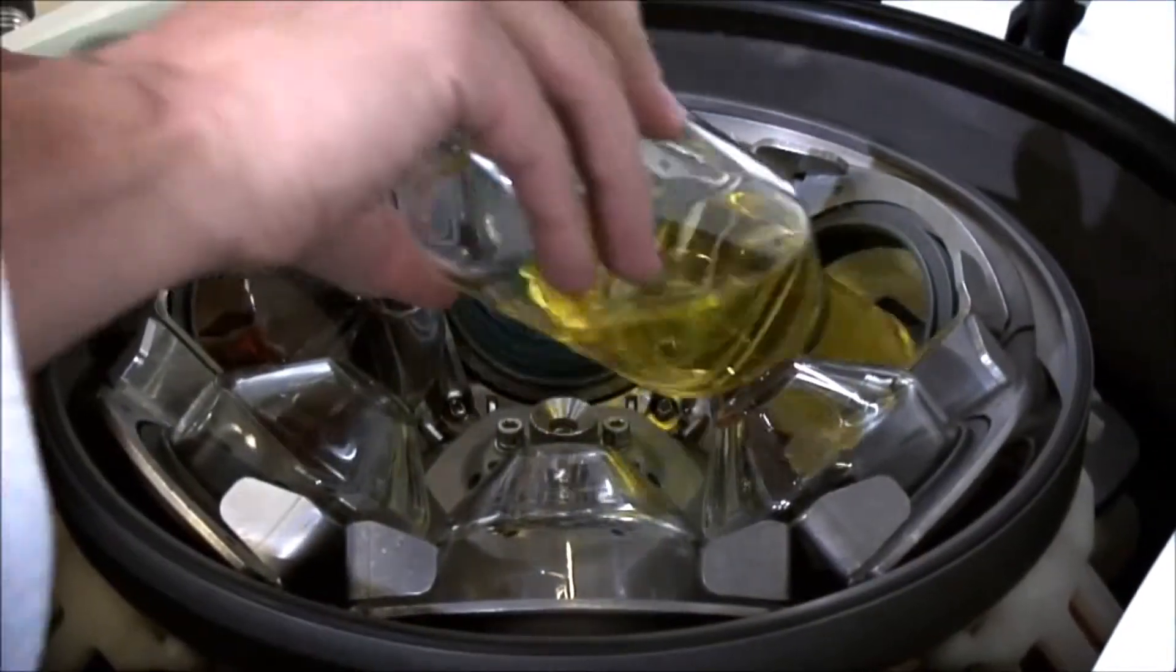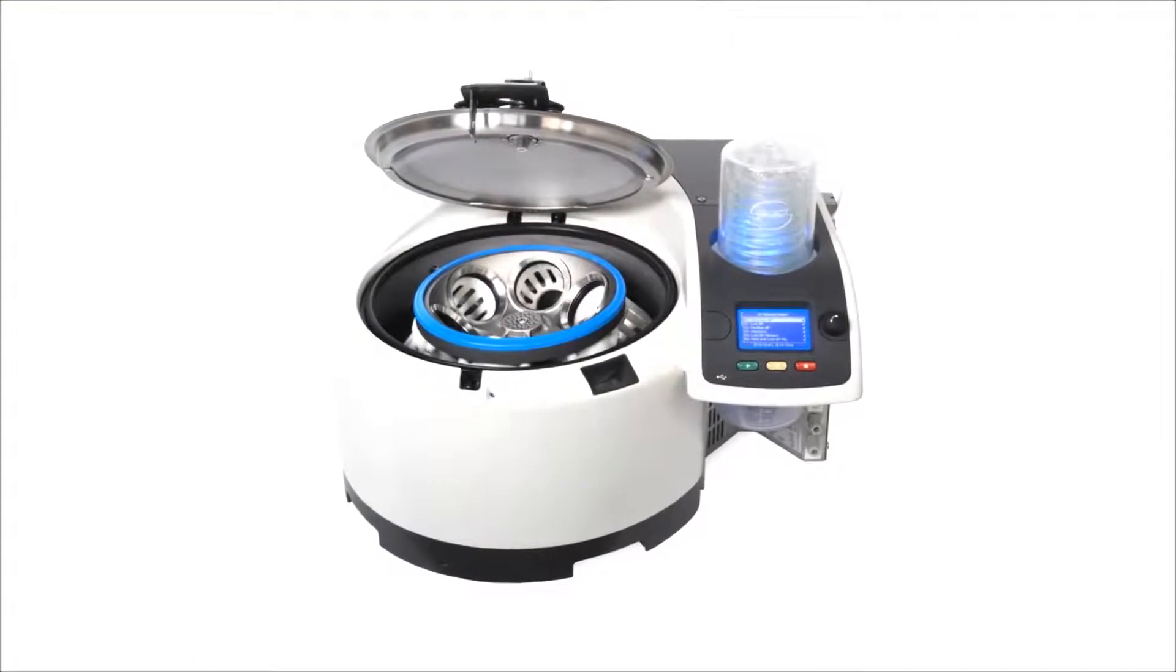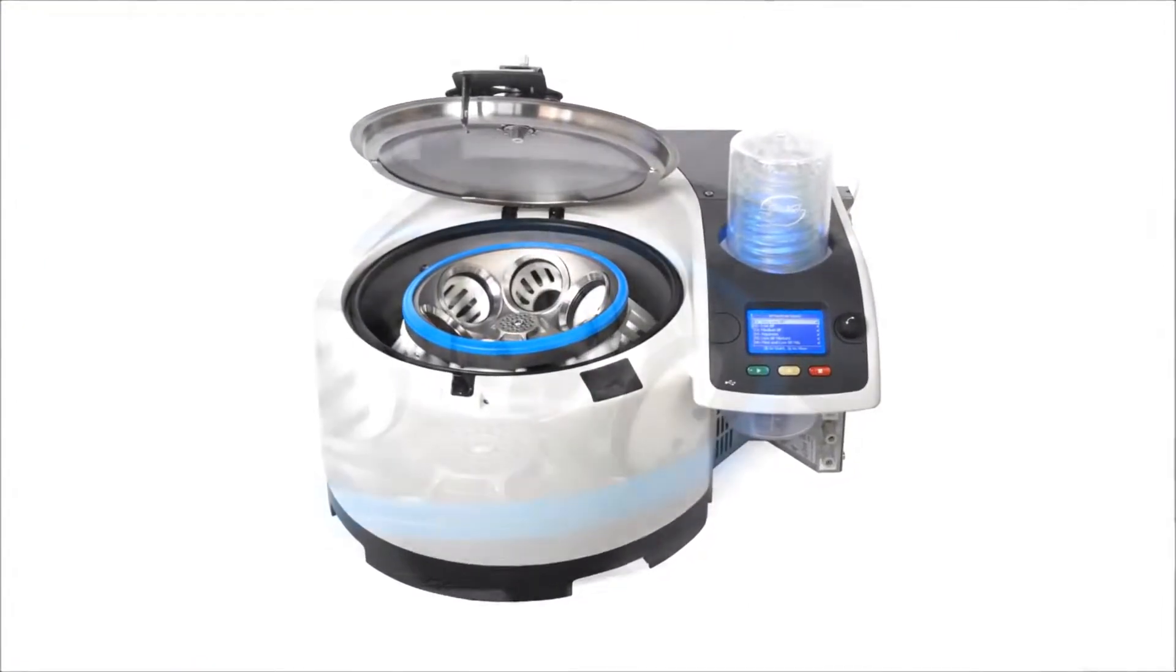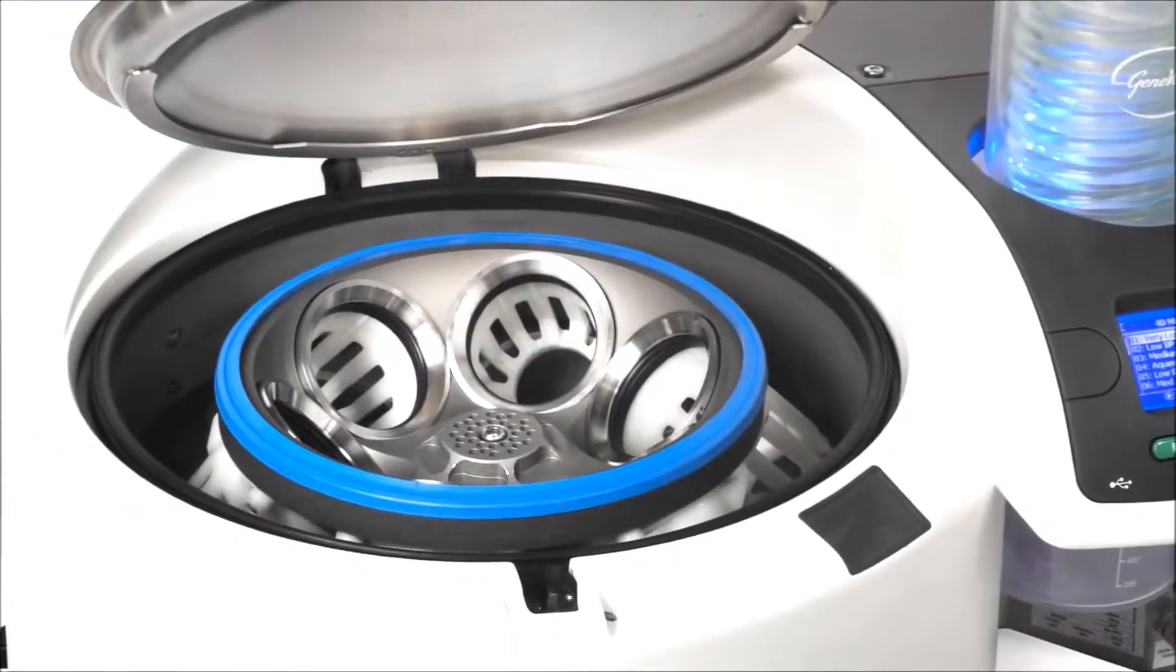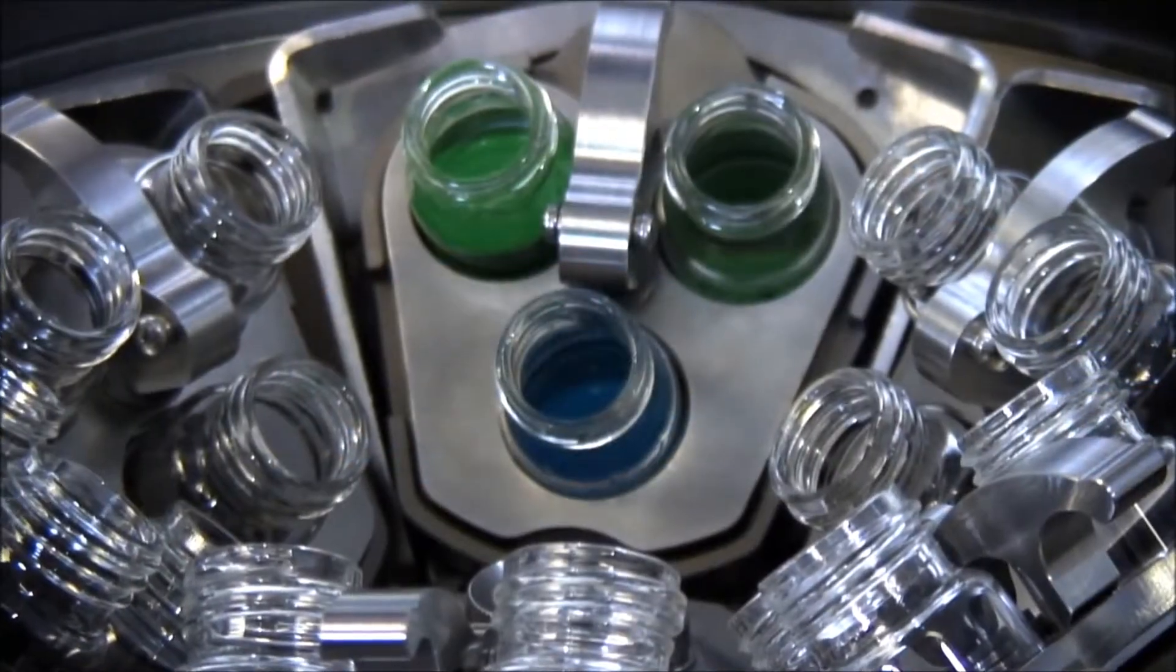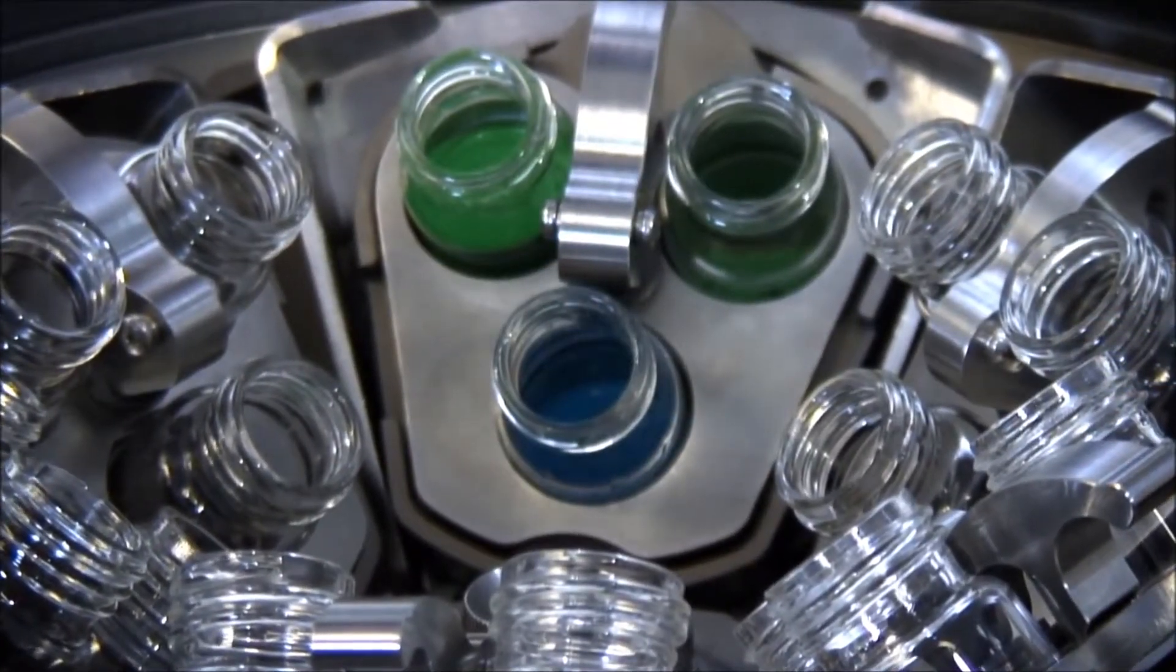The removable six-position flask rotor will accommodate a wide range of sample formats, drying or concentrating volumes from 50 milliliters to 450 milliliters.